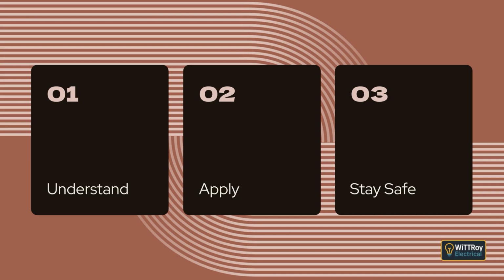Finally, we look at circuit arrangement. The installation must be divided into circuits in a way that avoids danger, reduces inconvenience when a fault occurs, and allows safe operation, safe inspection, safe testing, and safe maintenance. This means you do not put everything on one circuit. Instead, you divide the installation logically so that one fault does not shut down the entire building, and so that parts of the installation can be safely isolated for maintenance. The detailed rules are given in Clause 2.3, and those requirements must be followed.